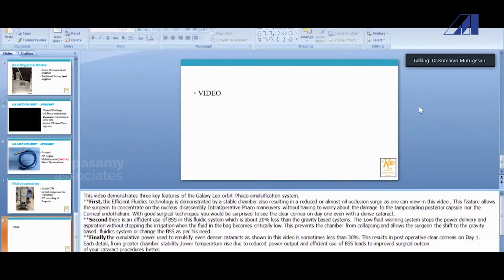So each detail, from greater anterior chamber stability, low temperature rise due to a reduced power output, and the efficient use of the balanced salt solution, leads to an improved surgical outcome and makes the movement of a cataract procedure always better. So the upcoming video is on a soft cataract. Here also you'll see that the chamber is actually very stable, and you'll see all the nucleus coming towards the phaco tip because of the effective real-time active fluidics and the fluidic stability.